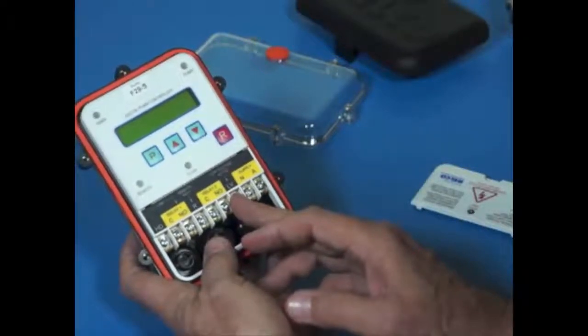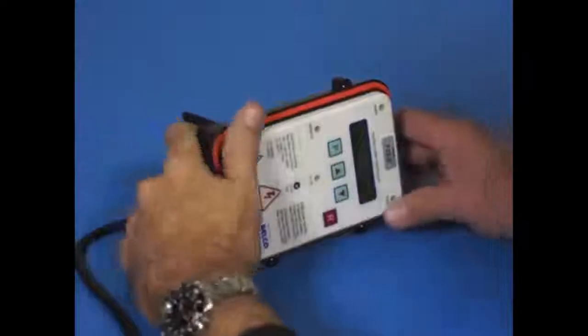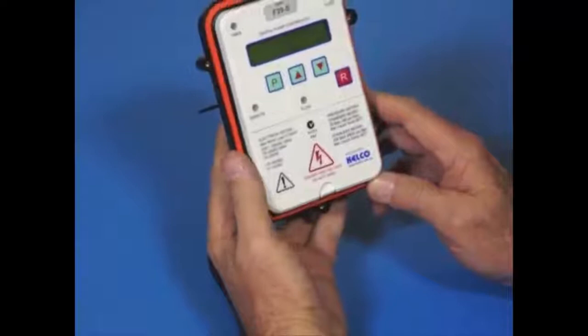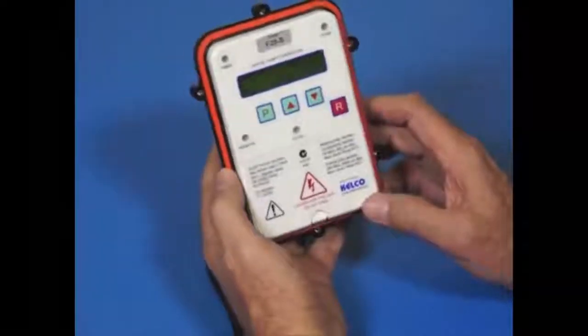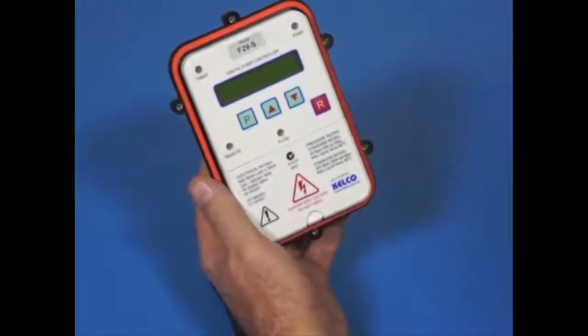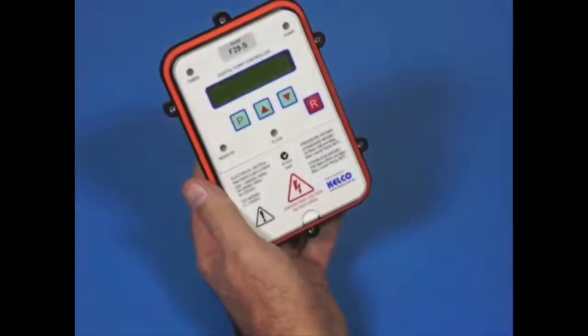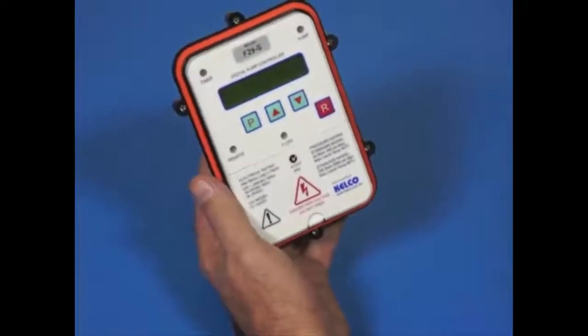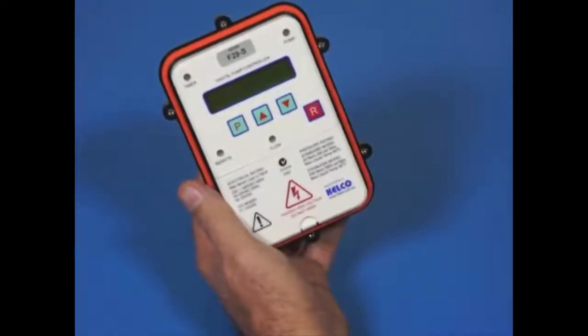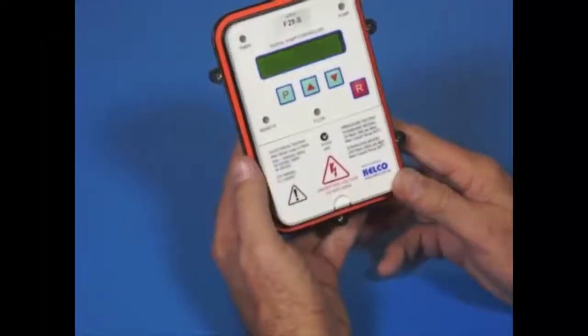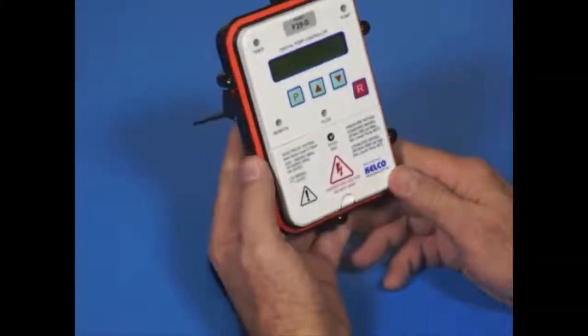I have here an F29 that's been wired up to the mains so I can demonstrate the functions of the device. The F29 has 11 built-in timers. The timers are individually programmable and they can do all manner of functions ranging from simple start up through to leak detection, anti-cycling, cyclic running and stopping, delayed restarting, there's a run-on timer. Each are individually settable and they can be used in conjunction with each other or singly.